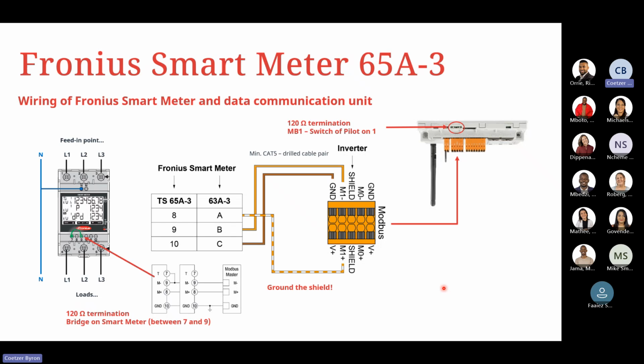Again, a few points on the wiring of the smart meters. Make sure that your 120 ohm terminating resistor bridge on the smart meter, between ports 7 and 9, is in place, depending on the meter that you are using. If you're using the TS 65A-3, it'll be ports 8, 9, and 10 that you're using. Whereas if you're using the older smart meter, the 63A-3, it'll be A, B, and C that you're wiring from directly from the meter itself.